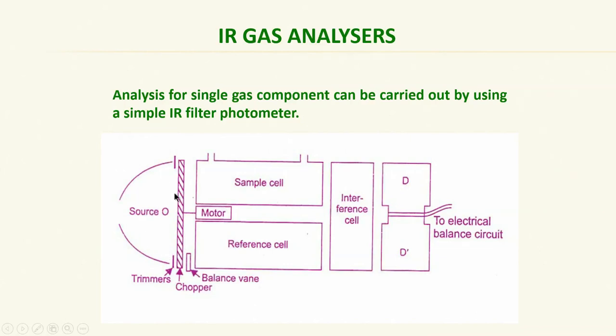Here we have a very simple primitive instrument which is used for quantitative analysis. I have a source of IR. It can be a silicon carbide rod or a thermocouple nichrome wire. This is the IR source. I have a chopper here for reference and standard, and this is a concave mirror to make the IR beam parallel. The sample cell, this is a motor for rotating this chopper. At one time when it cuts, radiation will pass through the top portion, and when it is rotating it will cut the top portion and radiation will be passing through the bottom cell.